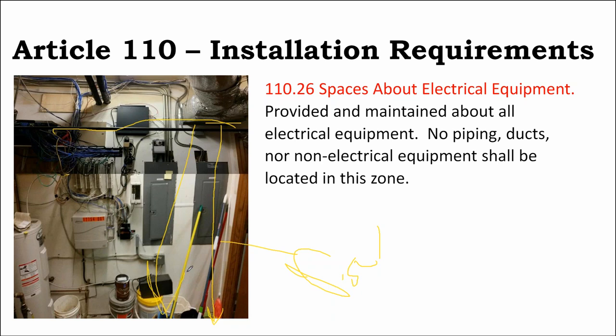Now, I recently did an off-grid house where we tucked the batteries into their own little alcove, their own little room that was built off the side of the building. And it turns out that room was an electrical code violation. For our project, the inspector didn't really care. But potentially, the problem with our alcove is that it's only about 5 feet, maybe 9 inches tall.